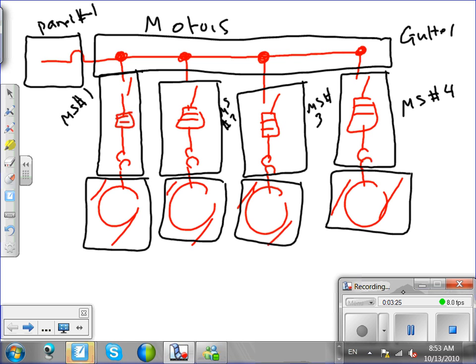So Brad, how do you think you connected this box into this gutter? Through a conduit and a wire. There will be a conduit and a wire, right? Or a cable. Most likely it's going to be EMT conduit and wires. So between all these boxes, there will be conduits and wires, okay? And our job is to size these wires. We can size the conduits, but today we're not interested in the conduits. We're going to size the wires at least. And we're going to size the disconnect, overcurrent protection device, overload, and branch circuit conductors and feeder conductors.